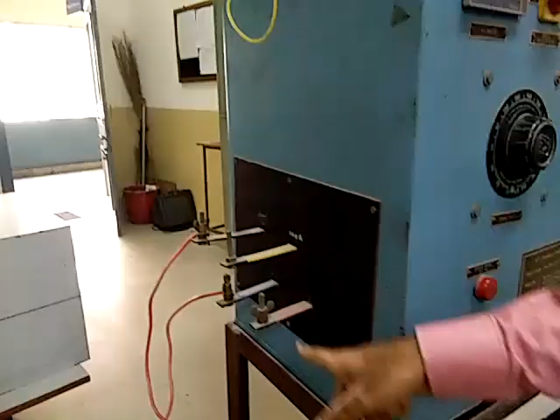So in this way we have seen the variation in AC and DC voltage, and the variation of current to be injected in the switchgear under test. Instead of this cable, we have to connect the current-operated switchgear under test, inject current through it, and note down the time after which this particular switchgear is going to trip. That way we take the readings of current versus time.